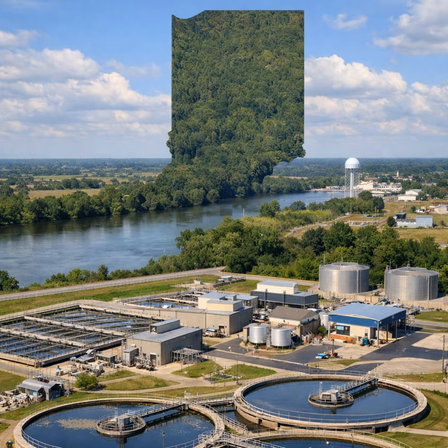Phosphorus removal. One is the Bardenpho process, a biological process which provides special conditions for both nitrogen and phosphorus removal. This system consists of five distinct reactors, which are respectively an anaerobic reactor, first anoxic reactor, first aerobic reactor, second anoxic reactor, and second aerobic reactor.